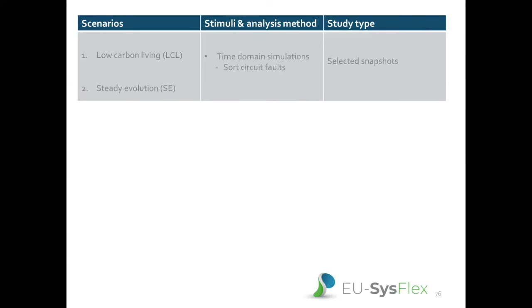Again, I'll be focusing on the more ambitious low carbon living scenario. And if we just go to the next slide, we'll see again that scatter of points. I'm going to touch on this again briefly, to remind you all, you've got the type 1, which is your high inertia, type 2, which is your high SNSP. Then you have the types in between, which are, in many ways, shoulder cases. And I just want to raise one point on these about how they can create that mixed localized issue, in that you have to bear in mind when you're in the 60% SNSP to 80%, so the high mediums, there's a whole variety of different ways you can reach that SNSP. We had a lot of fascinating cases. We had a few large sets and lots of wind. Equally, we had cases with lots of smaller generators and some wind.